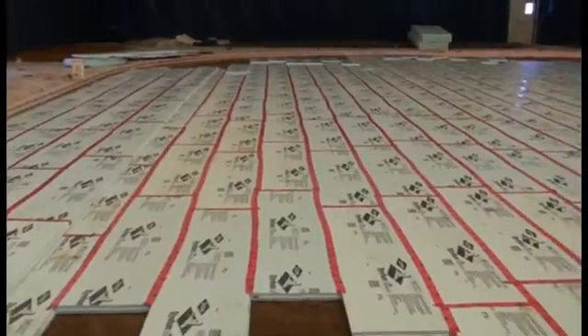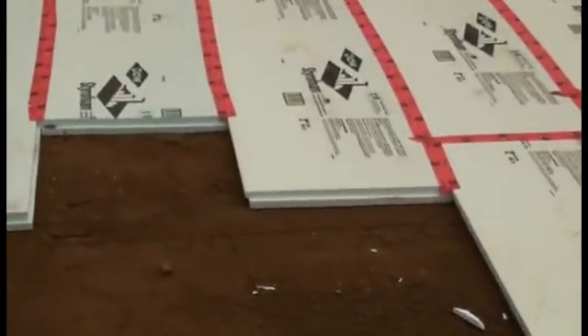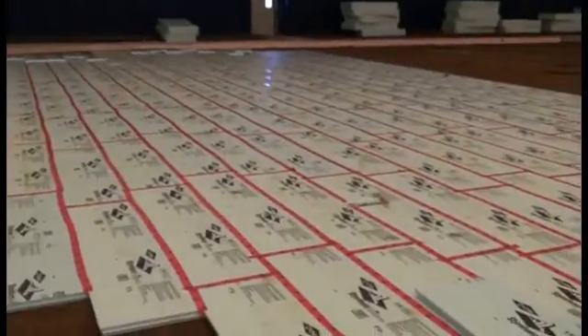Len's now focused on the styrofoam floor that's on top of the sand that's been brought to grade. That styrofoam is 4 inches thick, as I said. It's done in 2 lifts, and then it's all taped in sections, so there are no gaps, no rises, anything, because that has to be perfectly level within 3 to 5/8 of an inch.